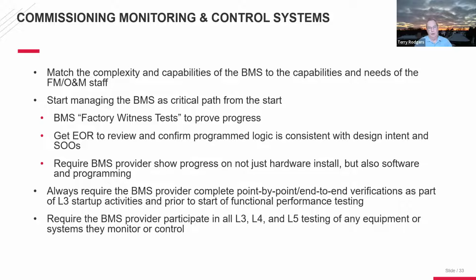If you don't do this in some manner or fashion, I've seen way too many times when I get called out in the field ready to do commissioning, the level 4 functional performance testing, and you get out there and there's temporary power and the guy's still trying to configure the systems, and there's all these hands in it, and it's very difficult to understand.